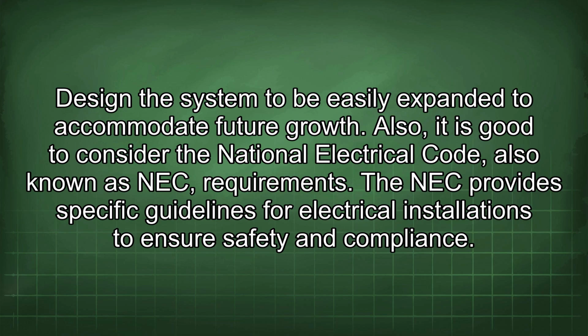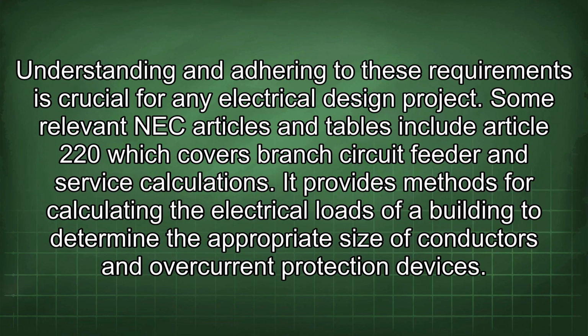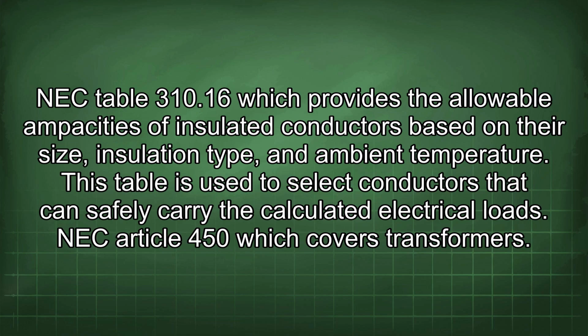Also, it is good to consider the National Electrical Code, also known as NEC, requirements. The NEC provides specific guidelines for electrical installations to ensure safety and compliance. Understanding and adhering to these requirements is crucial for any electrical design project. Some relevant NEC articles and tables include Article 220, which covers branch circuit feeder and service calculations. It provides methods for calculating the electrical loads of a building to determine the appropriate size of conductors and overcurrent protection devices. NEC Table 310.16, which provides the allowable ampacities of insulated conductors based on their size, insulation type, and ambient temperature.